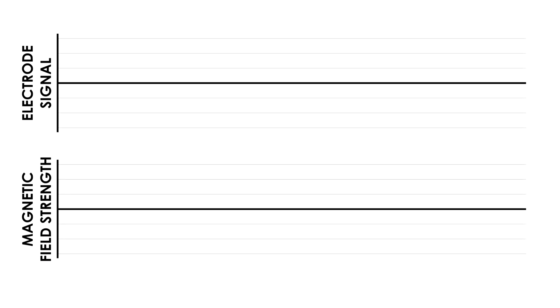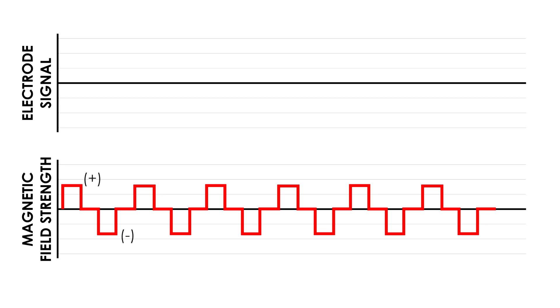This is a graph of a magnetic field which varies in strength as a series of biphasic DC pulses. Biphasic because it has negative and positive pulses, and DC because unlike a typical AC sine wave which is constantly changing, the waveform only has two values, on or off. Above is an example of the resulting EMF from a magnetic flow meter.